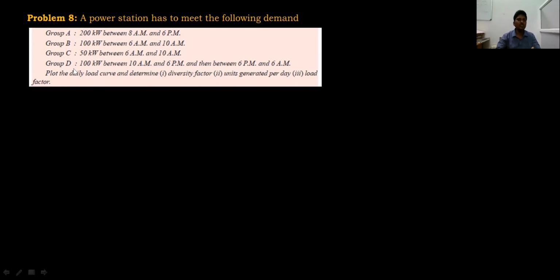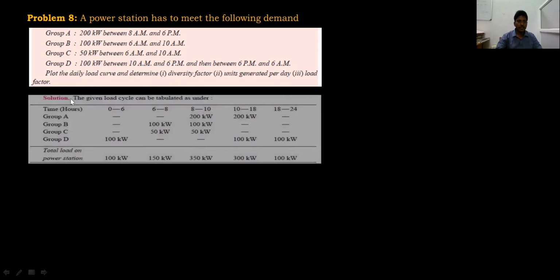After drawing, we need to cross-check again, because it's very important to draw a load curve here. First thing is I am reframing the data like this. I am dividing into 5 slots: 0 to 6, 6 to 8, 8 to 10, 10 to 18, and 18 to 24 hours. 0 to 6 means night 12 to morning 6, then 6 a.m. to 8 a.m., 8 a.m. to 10 a.m., 10 a.m. to 6 p.m., and 6 p.m. to night 12. So I have divided it into 5 categories.